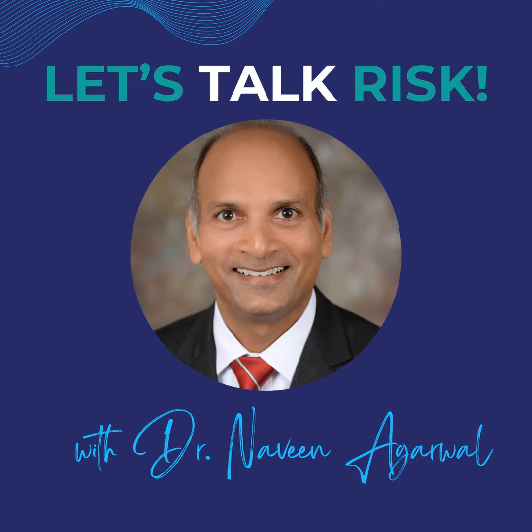So I'm a human factors engineer, working on the human factors and usability side. And to your point, we work with a use-related risk analysis, or a UFMEA, that it winds up being. And before that, there's generally a task analysis that should happen, right? That gets into a hazard analysis and then a URA. To your point of traceability, some people think of the task analysis as a URA. They're kind of the same thing, and I believe wholeheartedly they're separate things.